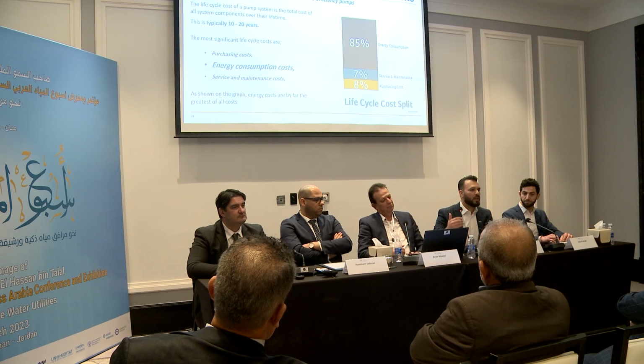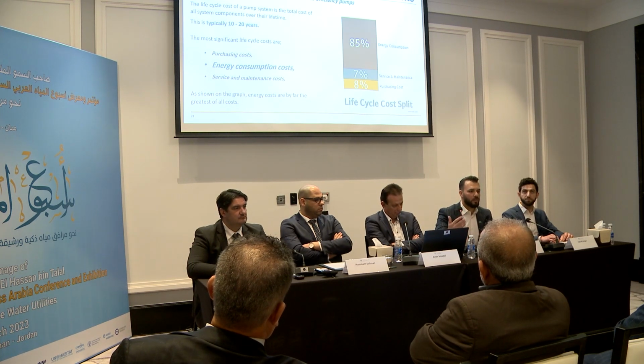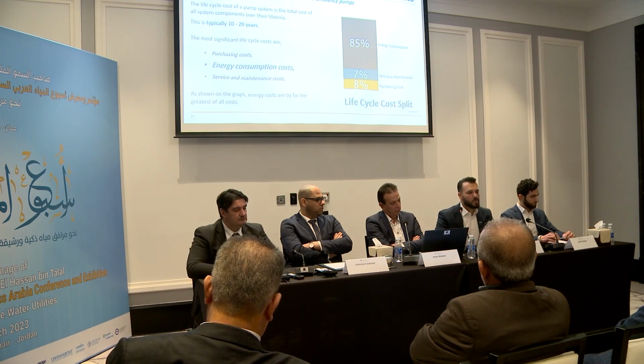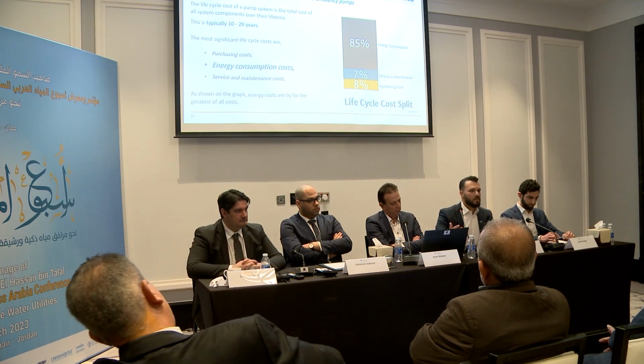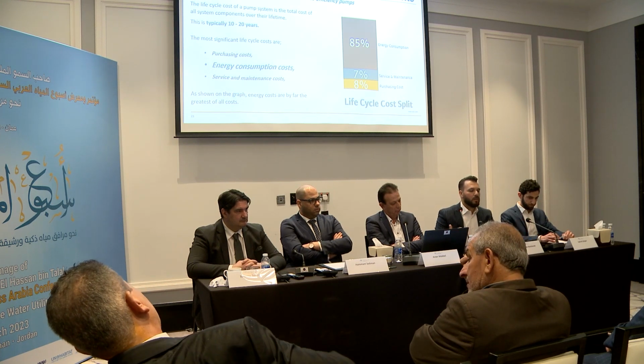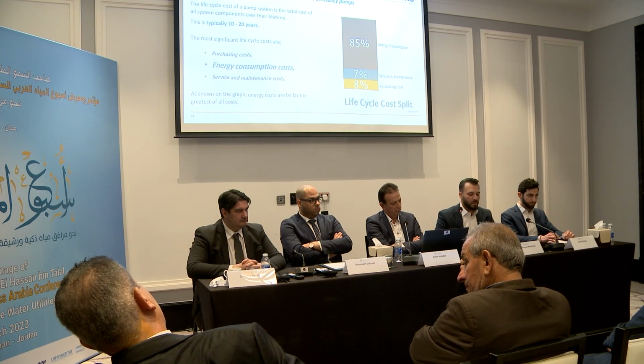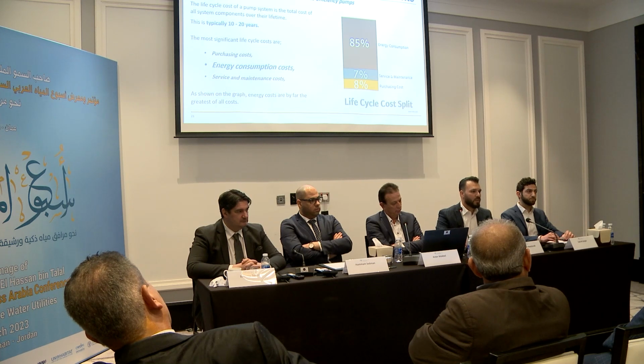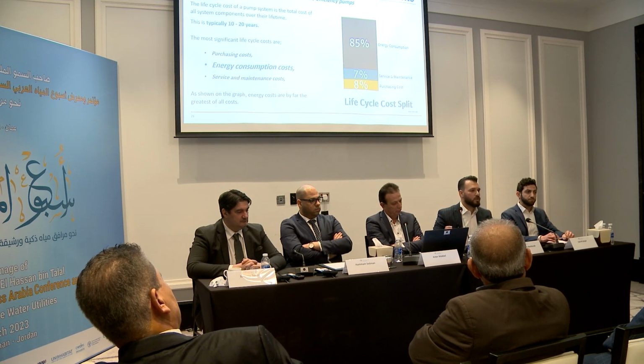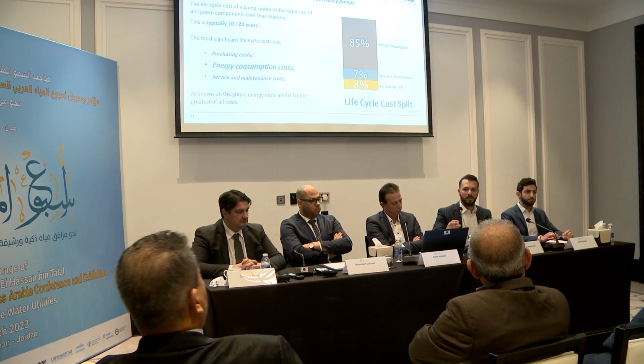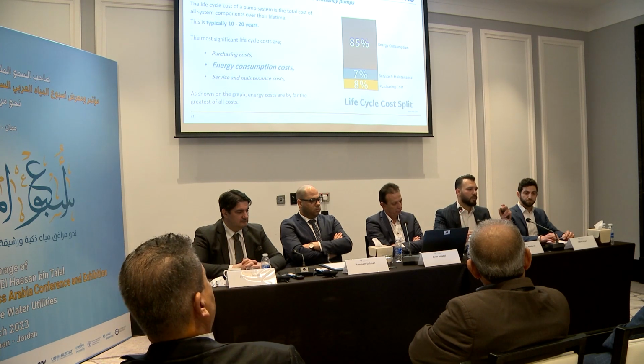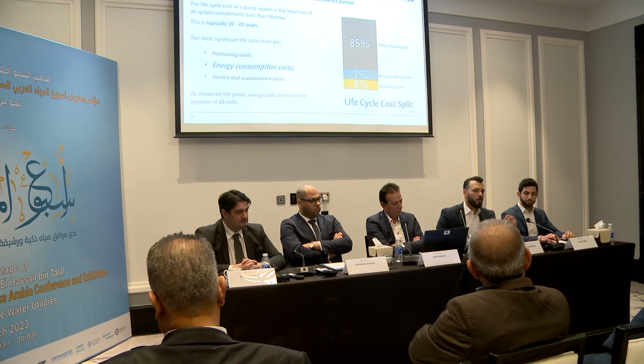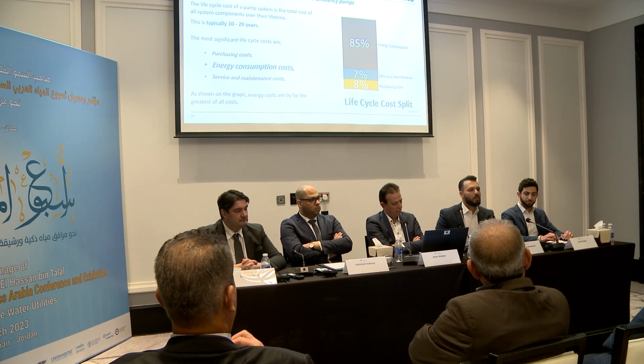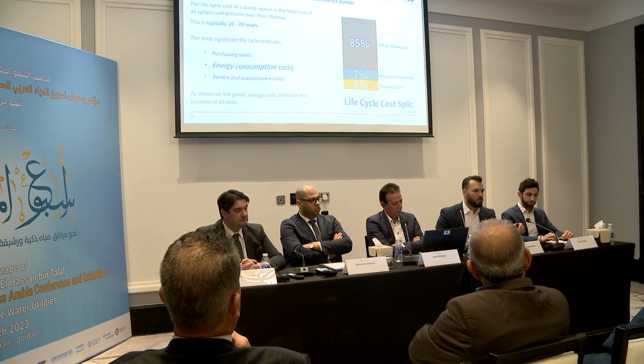But with pumps, you should always look at the life cycle cost of 10 years or 20 years. I buy the pump now, okay, then it's only 7 to 8% of the total life cycle cost, or more, depending on the manufacturer or the system that you have, but the bigger contribution goes to energy consumption. So when I evaluate a pump compared to another pump, I should know exactly what I'm going to pay now and 10 years forward.